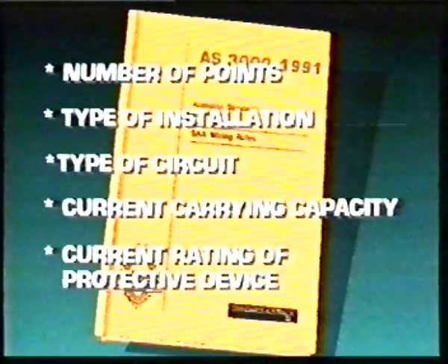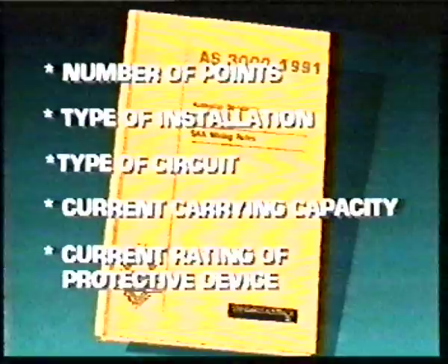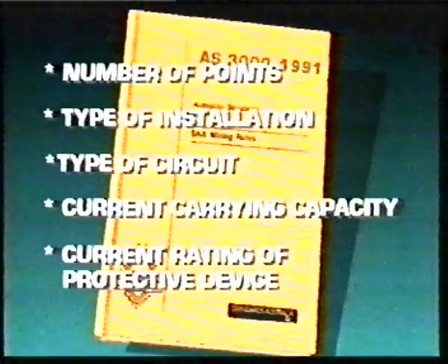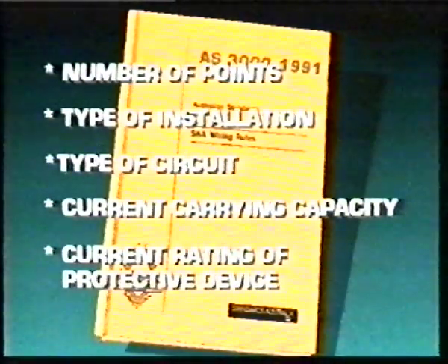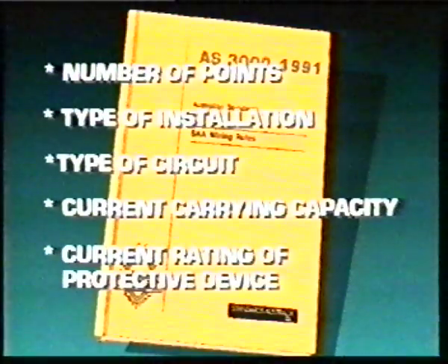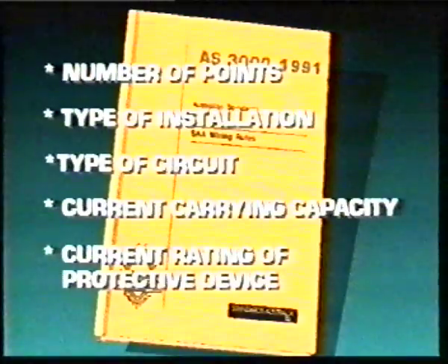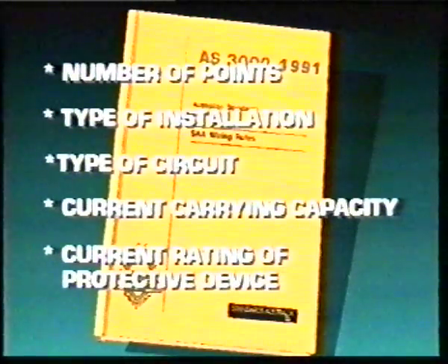AS3000 requires the number of points to be determined with respect to the type of installation, be it domestic or non-domestic, general or special purpose, the type of circuit, that is socket outlet, lighting points or fixed equipment, the current carrying capacity of circuit cable, and the current rating of the protective device.